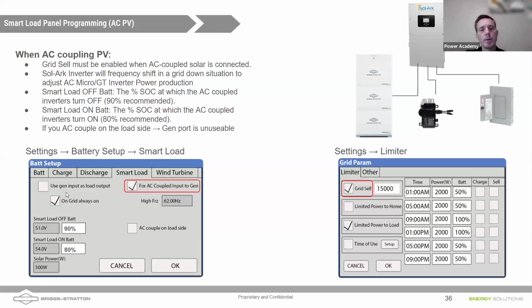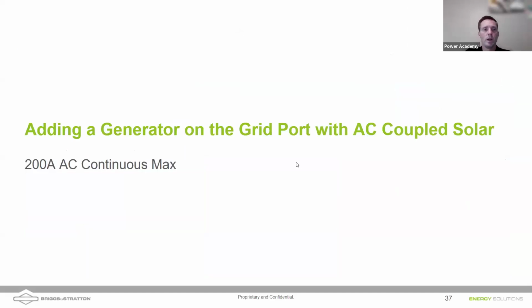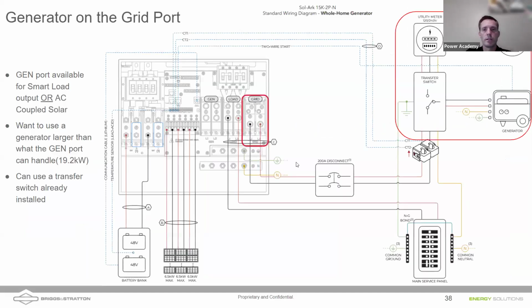And with an AC coupled system, you do need to make sure that you have grid sell enabled. You've got to be able to pass that extra solar back to the grid, because the solar cannot frequency shift if the grid is present, right? So if we've got grid voltage there and grid power there, then that frequency is dictated by the grid. Any other questions, Daniel? No, keep them coming, please.